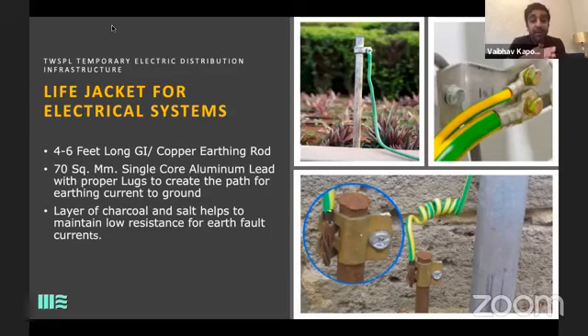The most difficult to work in is St. Regis, because your gensets are going on the 8th floor where there is no grounding. What we have done to overcome that, again, we have made a bucket kind of a thing. We made a 12 feet long pot, so that when there is earth flowing inside the ground, there has to be some ground to it. Or what we do on top, on the 9th floor only, the neutral earth has to be proper on that.